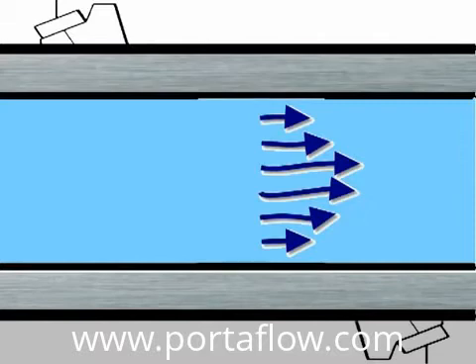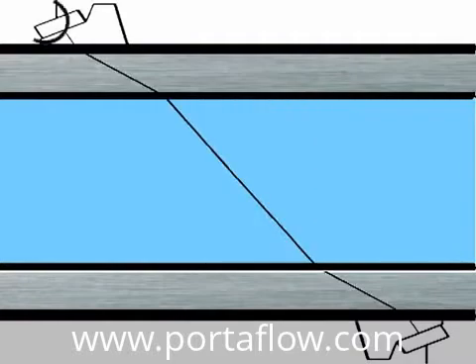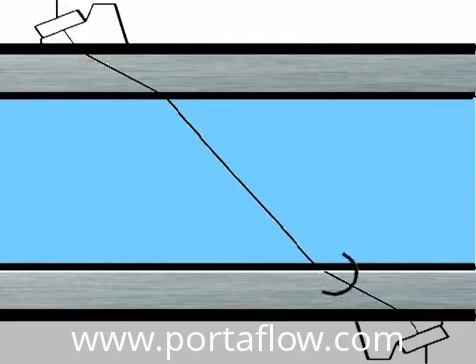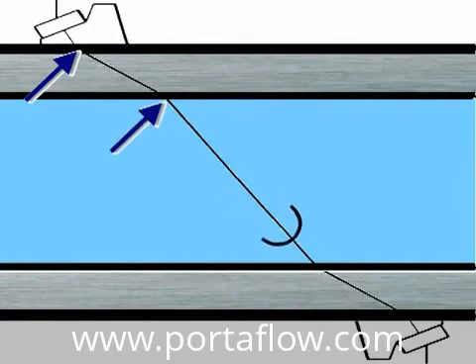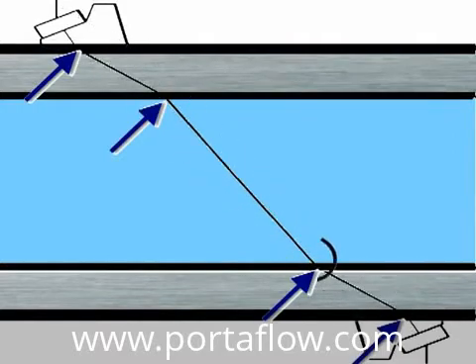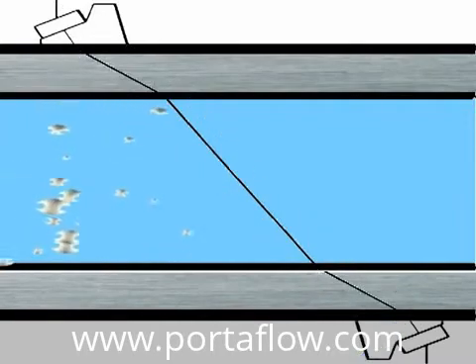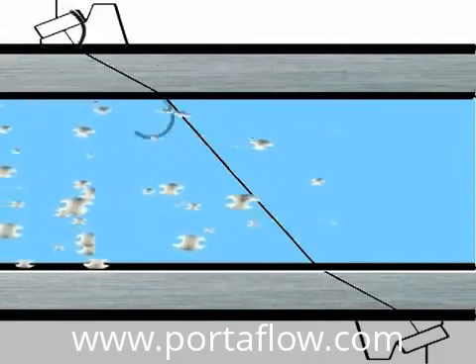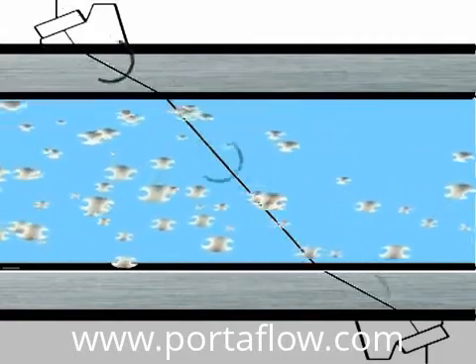The flow profile is pretty much a constant for laminar flow. To get both signals across, we have to firstly place the transducers very accurately on either side of the pipe. The refraction angles of the ultrasonic signal as it passes from one medium to another need to be known. This refraction angle is a function of the speed of sound in each of the materials. We also have to ensure that none of the materials through which the ultrasonic signal passes excessively attenuates or disperses the signal.